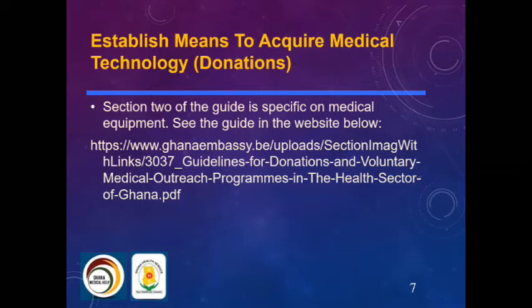And for new equipment, donation of new equipment must fit into the Ministry of Health Equipment Development Program. So donors intending to support healthcare activities in the public sector must go through this system to be able to donate new equipment. So all the equipment that is coming in must also follow the list and standards of the Biomedical Engineering Unit of the Ghana Health Service. So we go to the next slide.